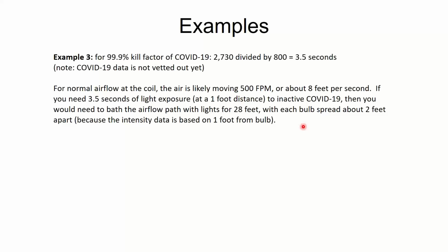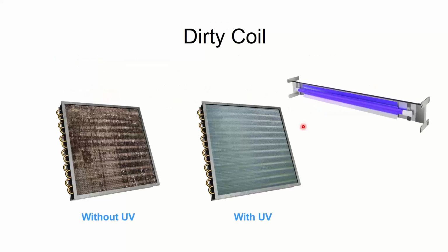It'll kill a little bit of it. So when we say UV lights kill COVID, it's not a lie. It's just not going to kill very much. And that's assuming the virus even gets entrained into the airflow and makes its way back to the UV light. It might not, based on our previous discussion with the filter. Viruses don't really give a crap about airflow. So if you get it back to the UV light at all, then you need a lot of intensity, which you can't get on a regular system to kill this guy.